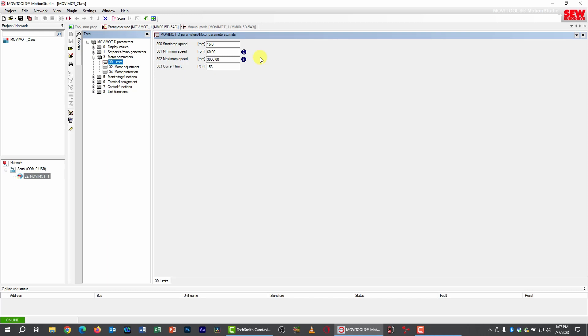And that is because these two parameters correspond to the F1 and F2 speed dials when they are being used to set the motor's minimum and maximum speeds. Now do remember when you're in binary mode, the F1 and the F2 dials provide the two speed setpoints. But when you're in RS-485 mode or fieldbus control mode, which is basically the same thing, the F1 and the F2 dials set the maximum and minimum speeds. Well, we have disabled those controls, and so these parameters are taking over that function.